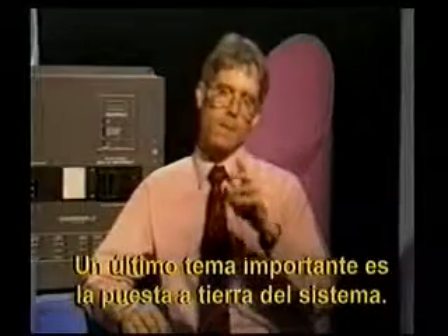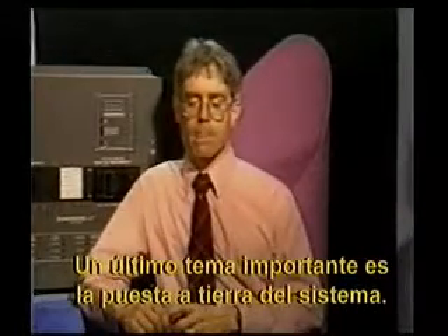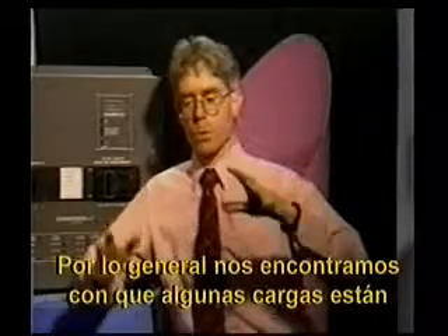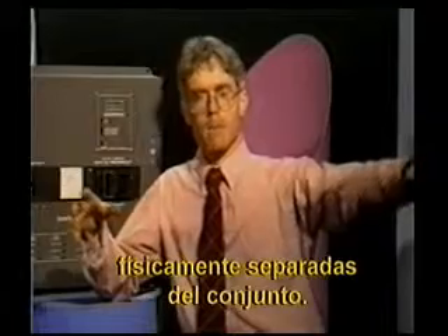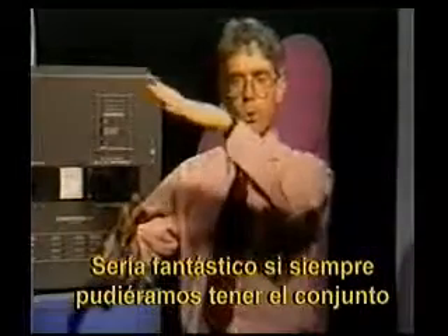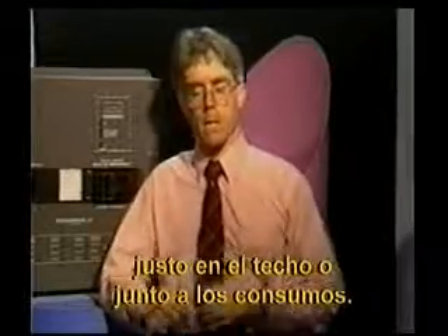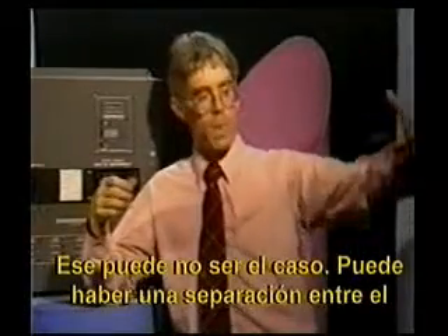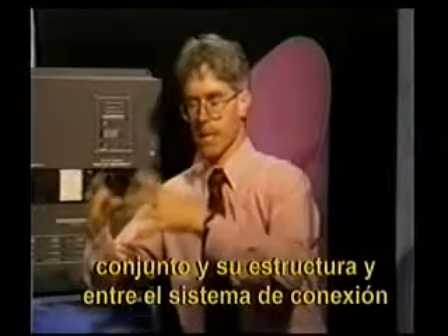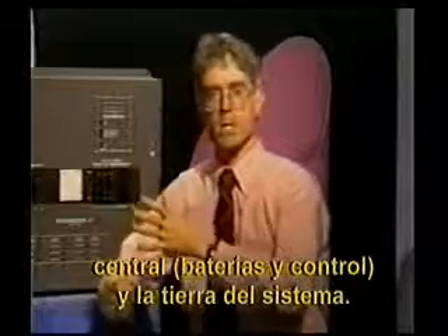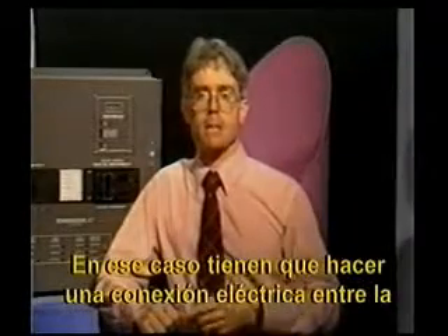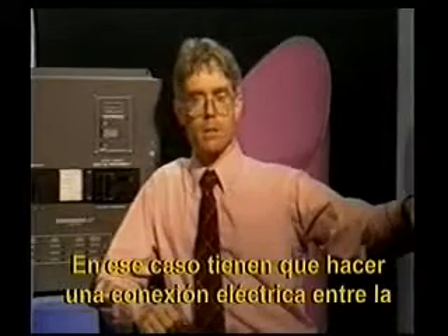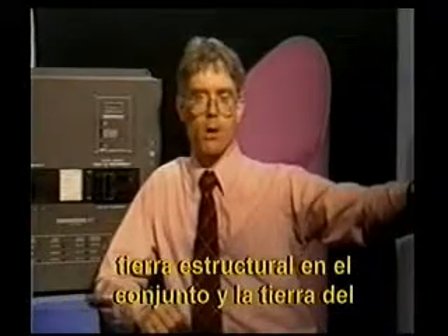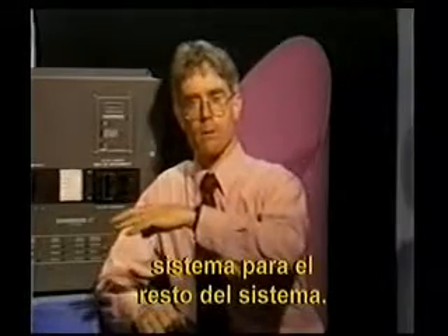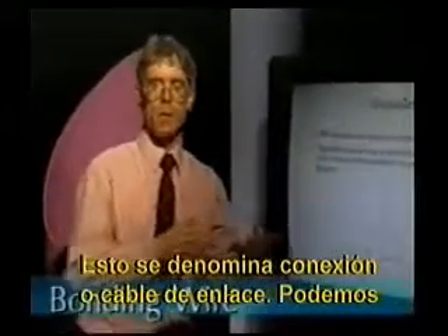A final issue that's real important to cover is system grounding. Typically, we're faced with the situation of having some loads physically separated from our array. It'd be great if we could always have the array right on the roof or right next to our loads. That may not be the case. We may have a separation between our array and its structure and our central wiring system, our batteries and control, and our system ground. In that case, you should make an electrical connection between the structural ground at our array and the system ground for the rest of the system. What this is called is a bonding connection or a bonding wire.